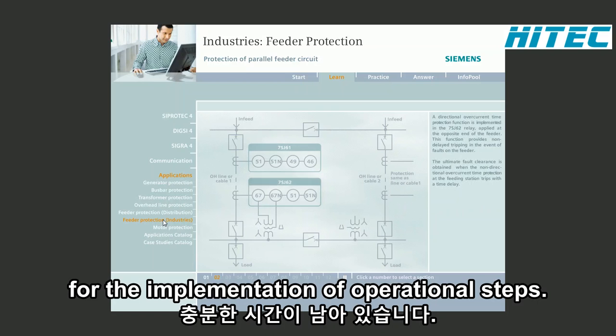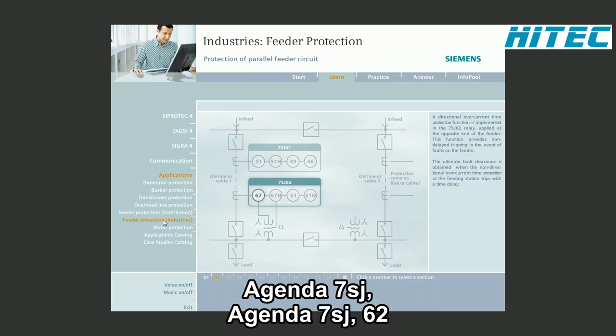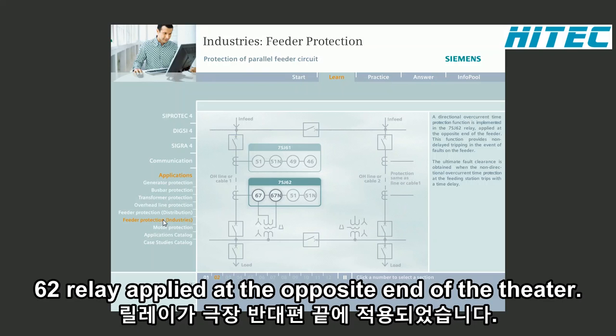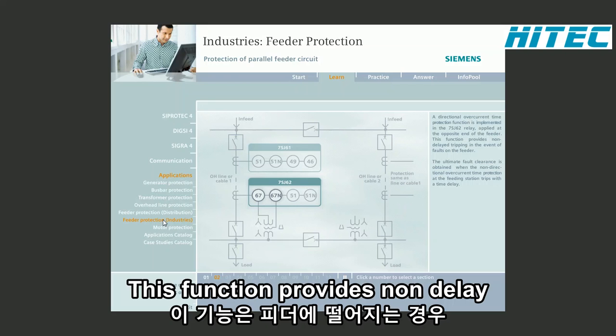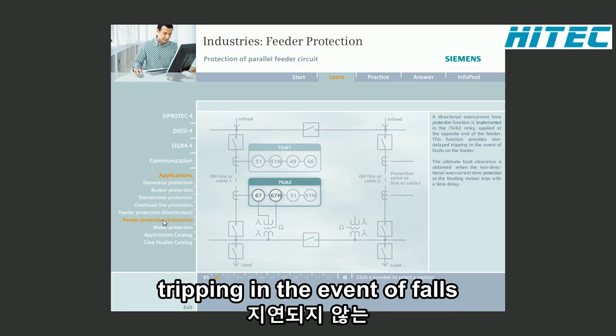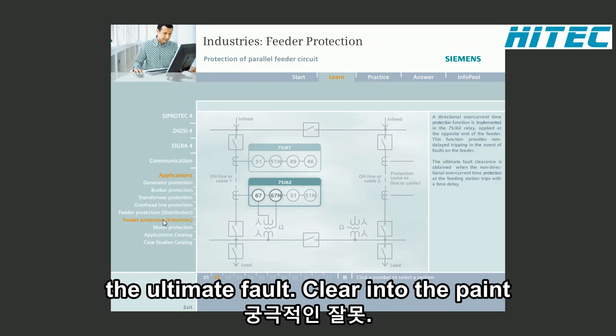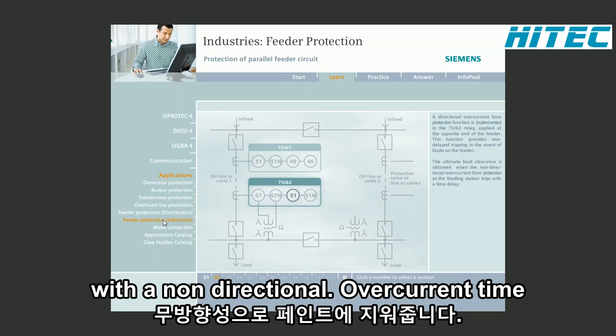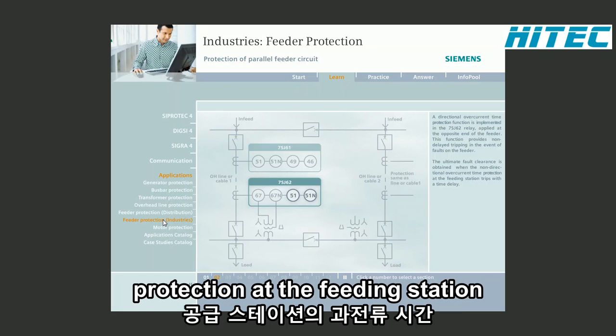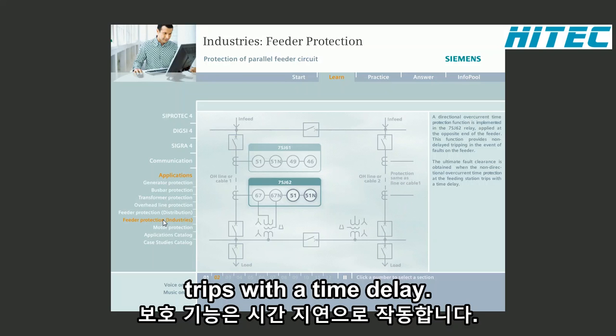A directional overcurrent time protection function is implemented in the 7SJ62 relay, applied at the opposite end of the feeder. This function provides non-delayed tripping in the event of faults on the feeder. The ultimate fault clearance is obtained when the non-directional overcurrent time protection at the feeding station trips with a time delay.